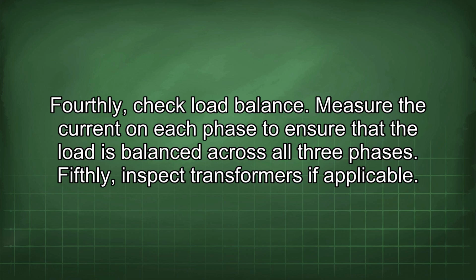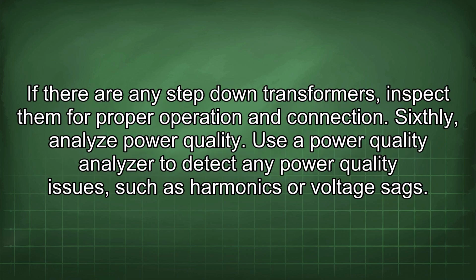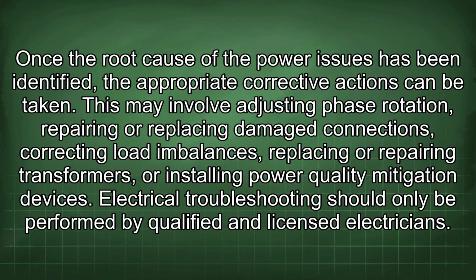Fifthly, inspect transformers if applicable. If there are any step-down transformers, inspect them for proper operation and connection. Sixthly, analyze power quality. Use a power quality analyzer to detect any power quality issues such as harmonics or voltage sags. Once the root cause of the power issues has been identified, the appropriate corrective actions can be taken.